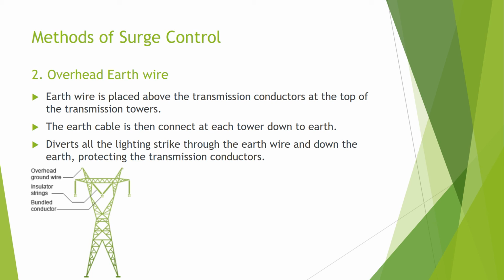Another type of surge control is the overhead earth wire method. The overhead earth wire with suitable cross-section is placed above the transmission conductors at the top of the transmission towers. The earth wires are then grounded at each tower. When lightning strikes, the electrical potential is diverted through the earth wires to the towers and then down to earth, protecting and preventing a direct strike on the transmission conductors.